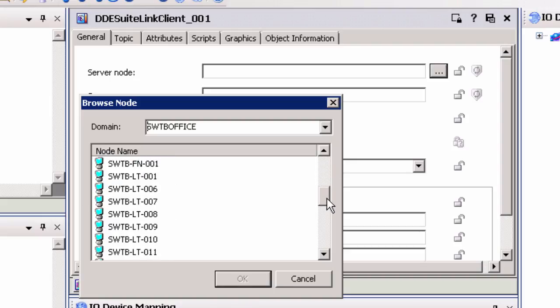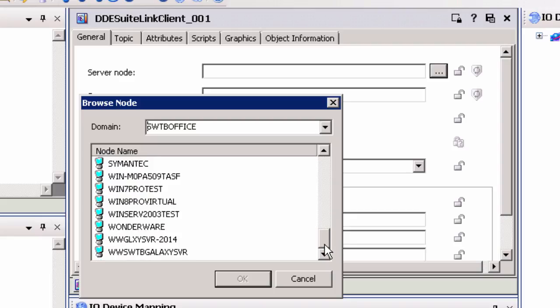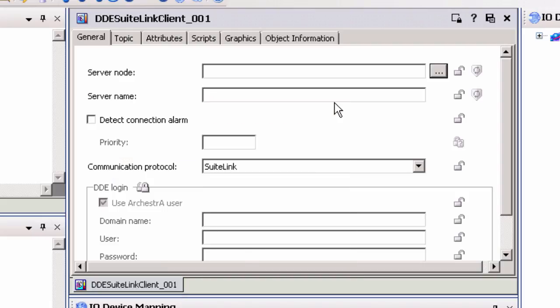Select the domain of the computer node where the TopServer is installed to display a list of available nodes. Next, highlight the appropriate node name and select OK. Next, enter Server_Runtime into the Server Name field. This instructs the DI Object to make a connection to the TopServer. Also, select SuiteLink as the communication protocol.